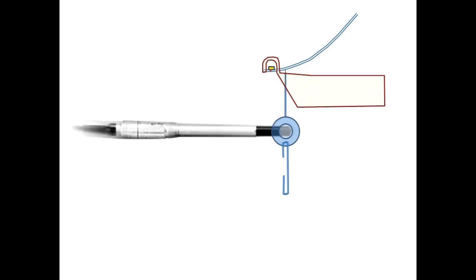First, we place the positioning mirror, we put the empty device and adjust the catheter to chamber distance, we remove the mirror, we remove the empty device, and finally we send the radiation source to the calibration position. Special care was taken about the levelness of the positioning mirror. For example, we used a laser beam for this type of adjustment.